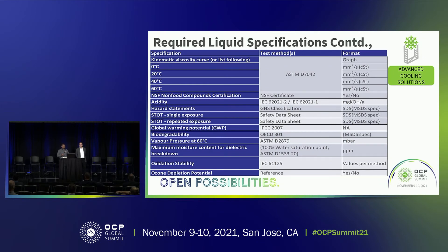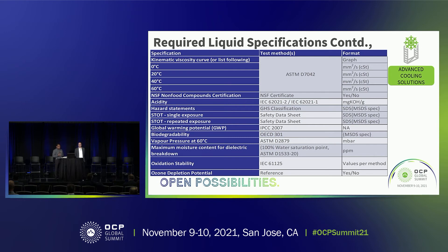Since we are looking at fluid at different temperatures, viscosity plays a key role. We are looking at 0, 20, 40, and 60°C. Acidity is something we would like to see before the fluid is immersed and then after immersion for a certain period or over a lifetime — what behavior is seen if any acidity appears during operation. One thing debated considerably, since these specifications involve single and two-phase players, is global warming potential. We have come to the conclusion to refer this test method so that people who are interested can report this information.